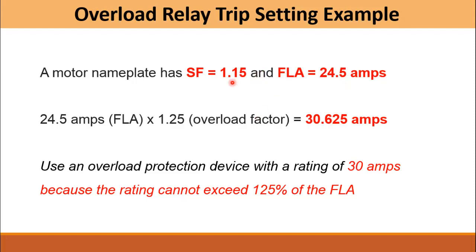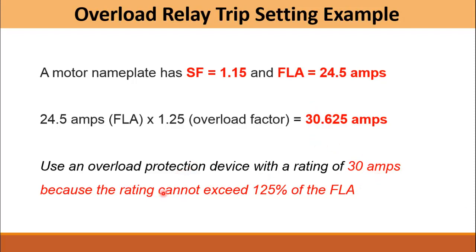Since the service factor is 1.15, the overload factor is 125%, giving a maximum setting of 125% × 24.5 = 30.625 A. The standard overload device comes in a 30 A rating, so we select 30 A because the rating cannot exceed 125% of the full load ampere. If you cannot find the exact current rating, select the relay with the next lower setting from the maximum calculated current.